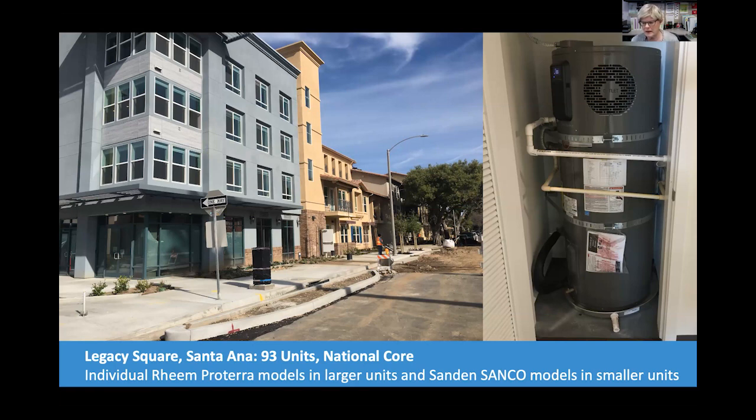And increasingly, the energy codes are recognizing that this is a problem. And I know I've seen that in the California code, in the next cycle, they're not going to allow heat pump water heaters to be in conditioned space unless they have direct supply and exhaust of the air, so that they aren't cooling down the air, they aren't pulling the heat from the air. So whether it's retrofit or new construction, that's a very real issue you have to think through when you're putting in the water heater heat pumps.